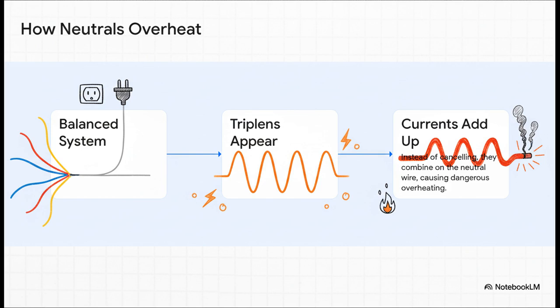Here's where it gets really scary. Normally, in a big three-phase system, the currents on the three main wires are supposed to cancel each other out, so the neutral wire just hangs out carrying almost no current. But triplens don't play by those rules. They don't cancel, they do the opposite. They're all in sync, so they gang up and add together on that poor, unsuspecting neutral wire. Suddenly a wire designed for almost zero current is carrying a massive load, turning it into a red-hot heating element. And yeah, that's a massive fire risk.